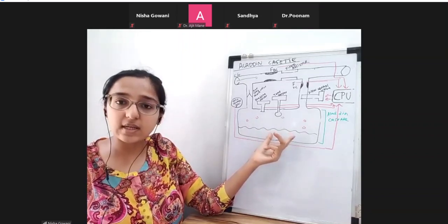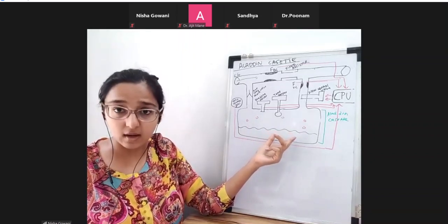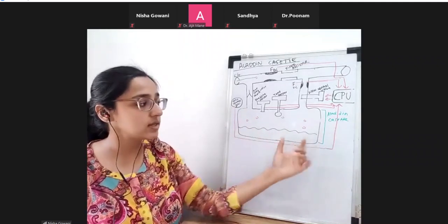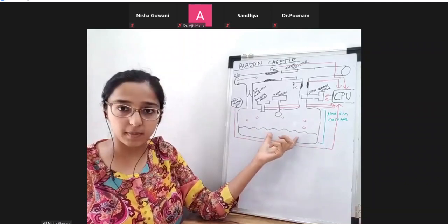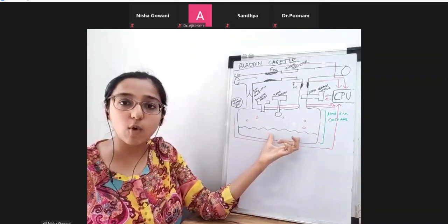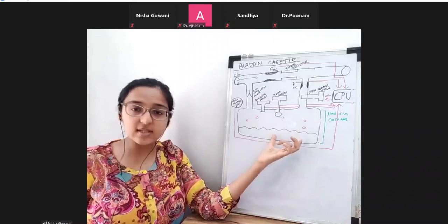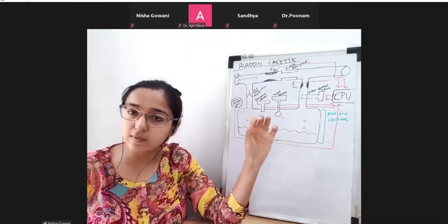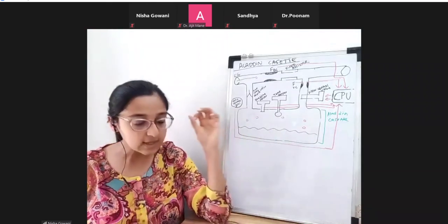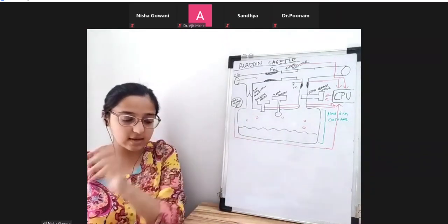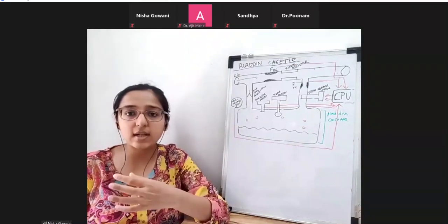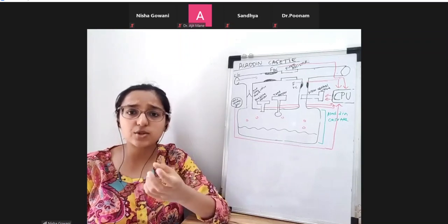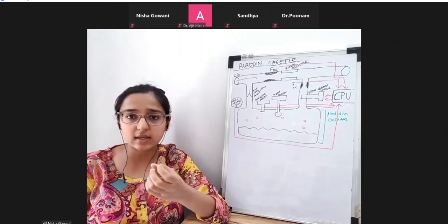There is a facility in the anesthesia machine wherein there is a fan. A fan gets activated and warm air is passed over this cassette, so this anesthetic liquid gets warmed up. This fan gets activated in two situations: during desflurane induction and maintenance, and during sevoflurane induction. Now there are certain safety features in this. There is a Link 25 system, wherein you ensure that a hypoxic gas mixture doesn't get delivered to the patient.